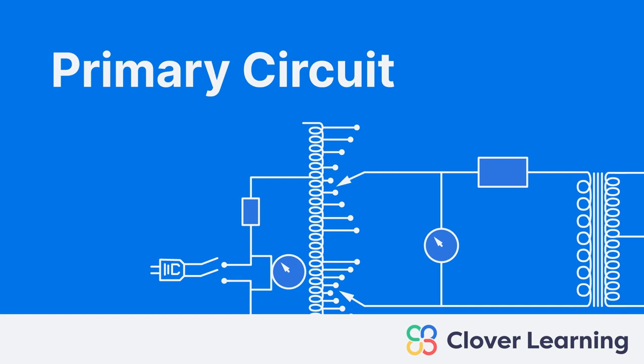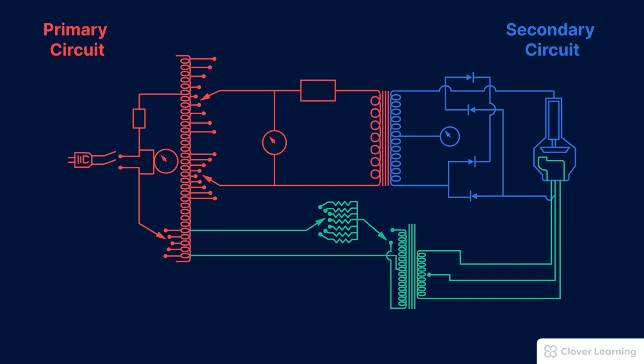This lesson is the first in a series about the x-ray circuit, and we'll be talking about the primary circuit. The complete x-ray circuit is actually three combined circuits: the primary circuit, the secondary circuit, and the filament circuit.